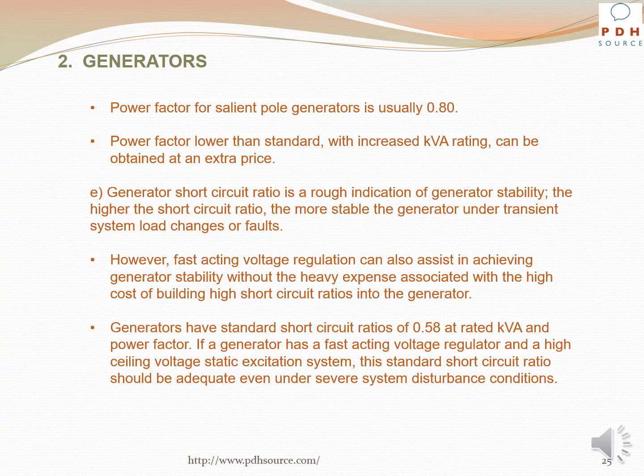Generator short circuit ratio is a rough indication of generator stability. The higher the short circuit ratio, the more stable the generator under transient system load changes or faults. However, fast-acting voltage regulation can also assist in achieving generator stability without the heavy expense associated with the high cost of building high short circuit ratios into the generator.